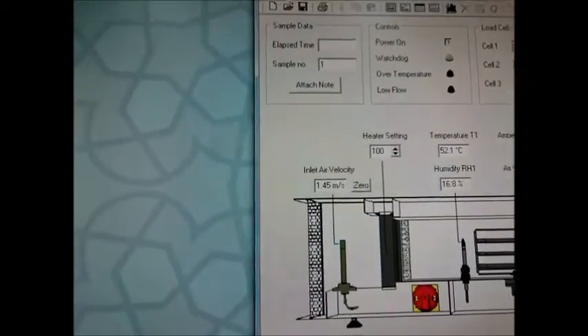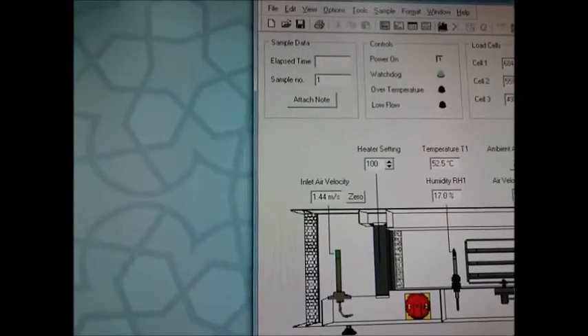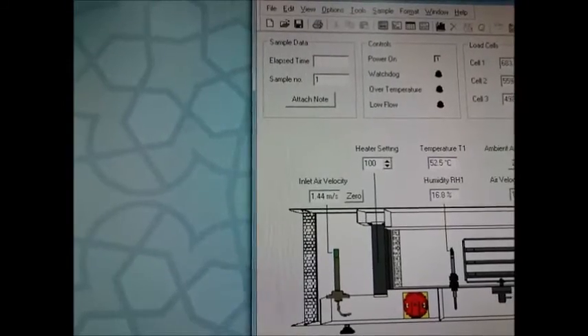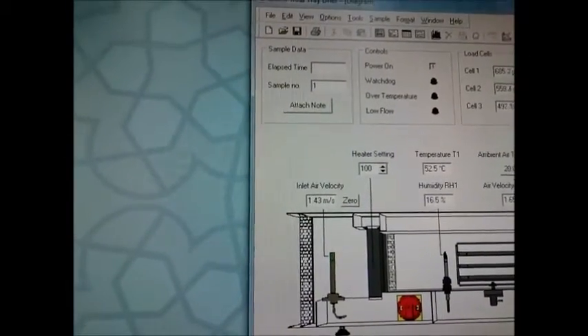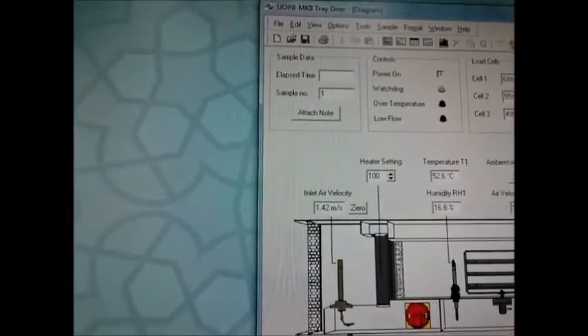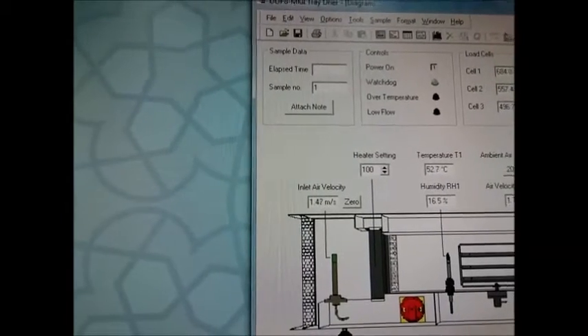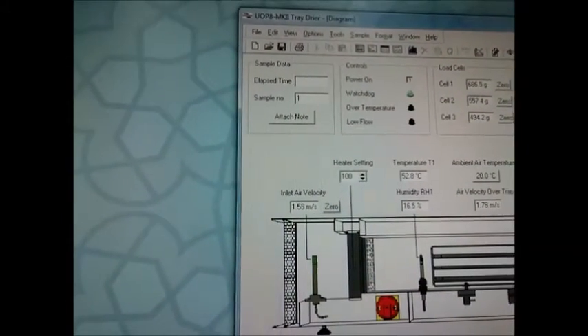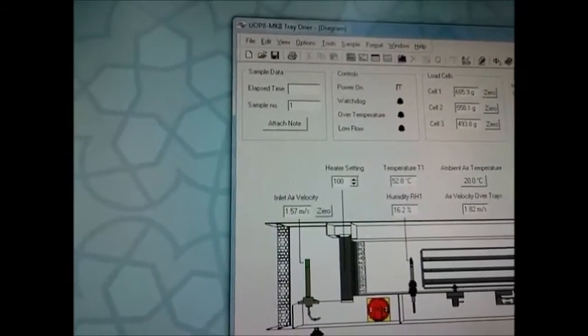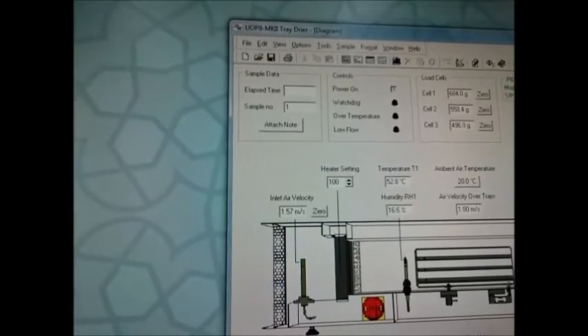Also notice that we had set the temperature at 65, so we need at least 30 minutes for the temperature to be stable.